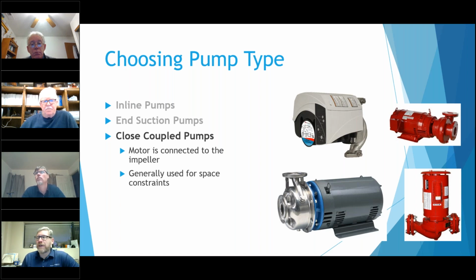So I only kind of recommend it if you really have a space constraint that you need to pull them out. These with the end suction, they're a little bit harder to pull out too, especially if this isn't piped in right. You want to make sure that there's no pipe strain. There's been a lot of jobs where I've gone out and pulled this out, and the whole volute will actually move because it's kind of put in a bind. It tears up bearings and seals and makes the pump noisy. In the worst case, I've seen where the volute's actually cracked on these pumps. But that's where these are usually used. It's almost always space constraint.